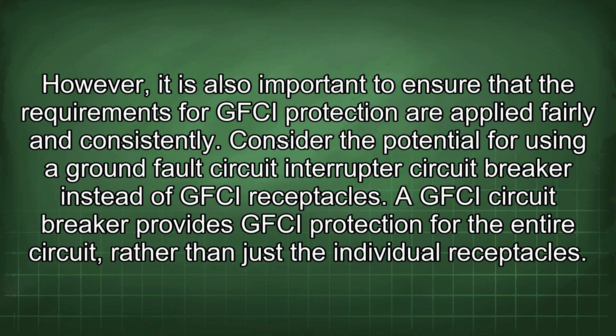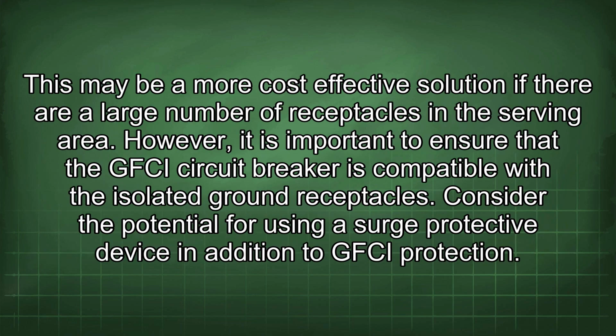Consider the potential for using a ground fault circuit interrupter circuit breaker instead of GFCI receptacles. A GFCI circuit breaker provides GFCI protection for the entire circuit rather than just the individual receptacles. This may be a more cost-effective solution if there are a large number of receptacles in the serving area. However, it is important to ensure that the GFCI circuit breaker is compatible with the isolated ground receptacles.